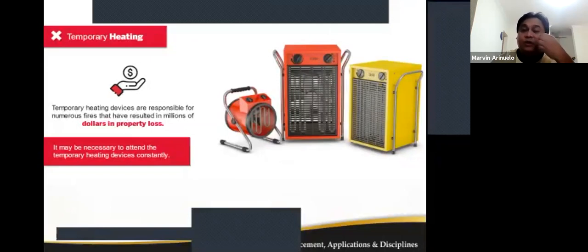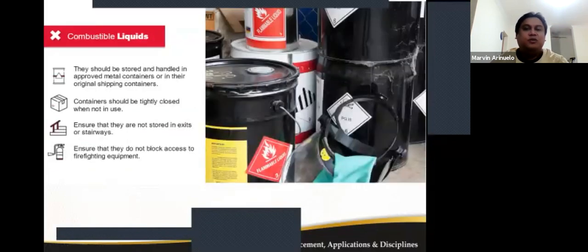temporary heating, especially during winter. Salamanders and other temporary heating devices are normally responsible for numerous fires, resulting in millions of dollars in property loss. When temporary heating devices are used, they should be visually inspected every half an hour by a fire watcher or a safety officer or inspector to ensure that those devices are not overheating and that combustibles have not blown over. So that's one thing: overheating is the issue of fire, and another is blown over or fallen material near them. To attend to the temporary heating device constantly, any object that is too hot to touch should be moved or the heating device should be relocated to a much safer area.